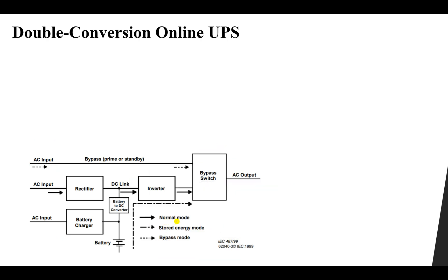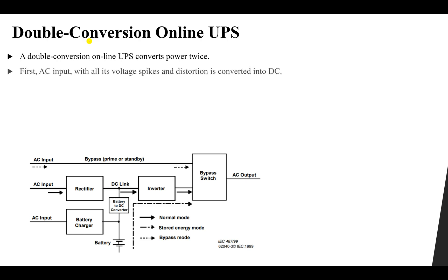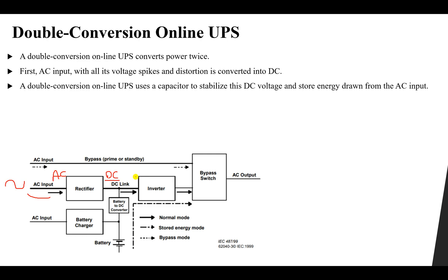The second mode is the normal mode, in which we have a double conversion process. A double conversion online UPS converts the power twice. First, the AC input — with all its voltage spikes and distortions — is converted from AC into DC using a rectifier. Then we have a DC link capacitor which stabilizes this DC voltage.